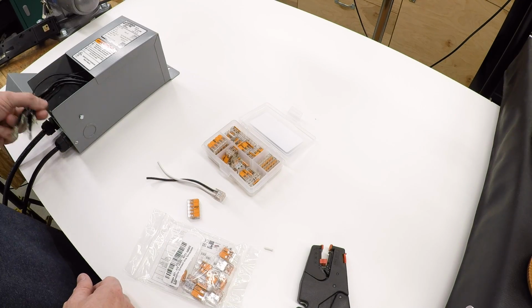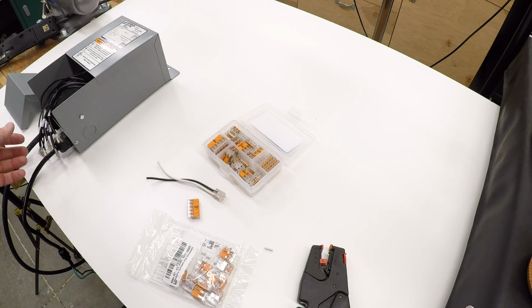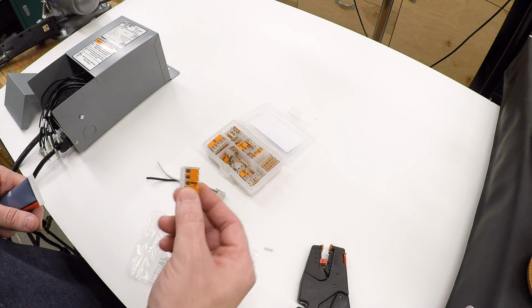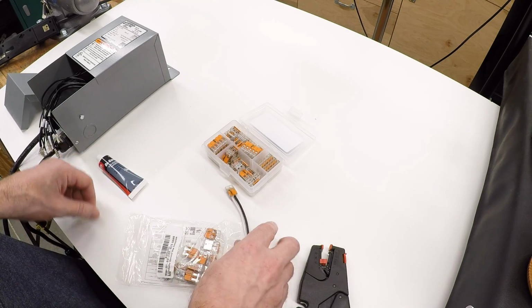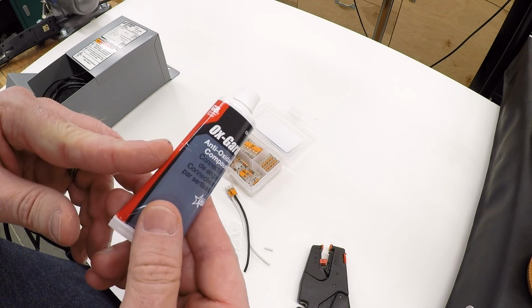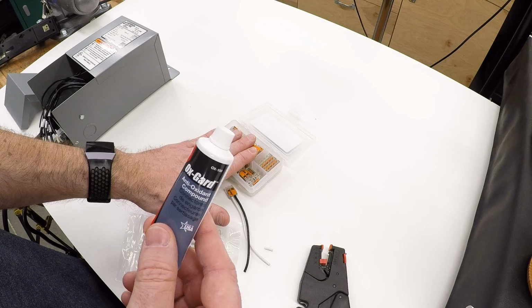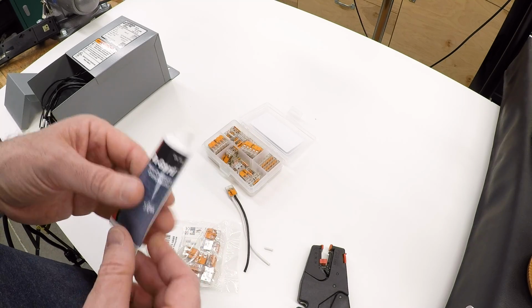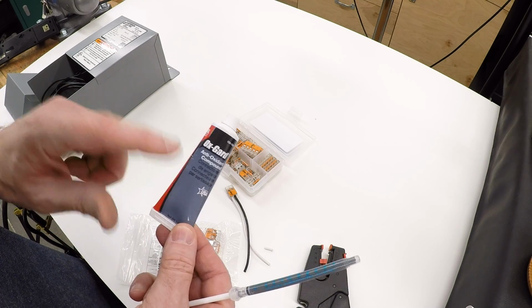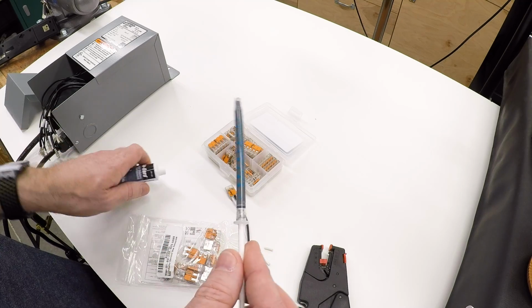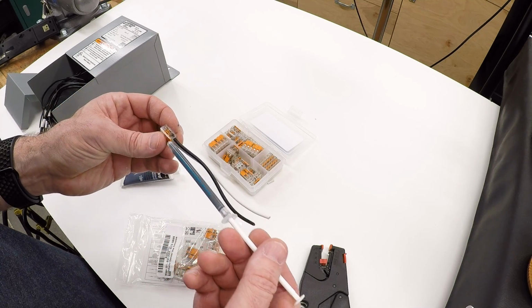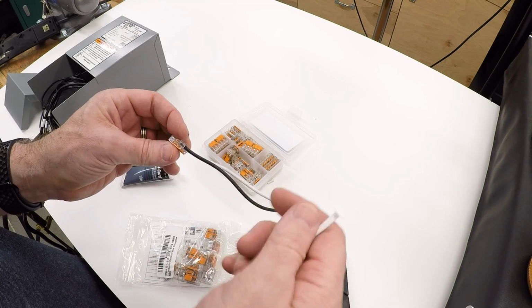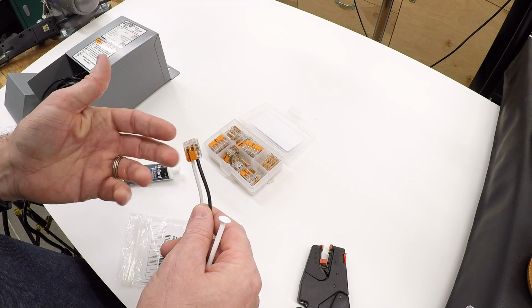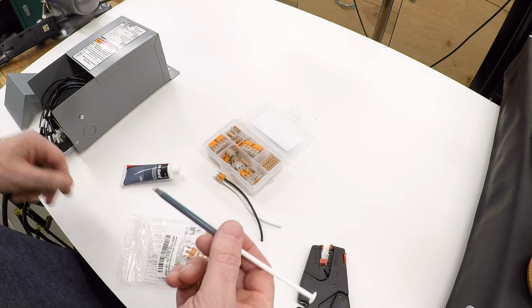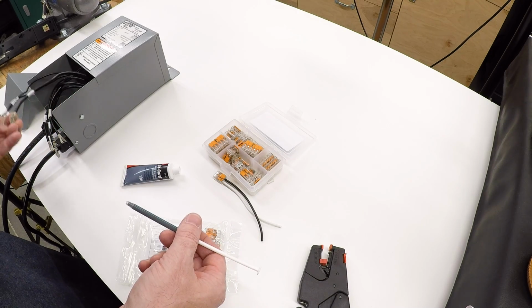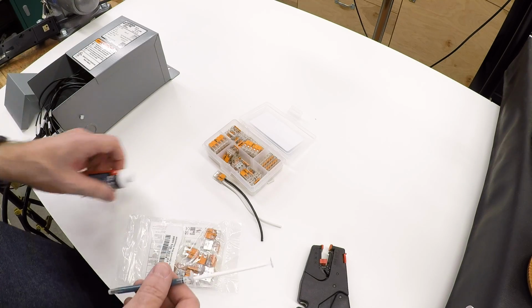One thing about this is that this transformer has aluminum wire. To make aluminum wire connections to nuts like these that have copper, you have to use some kind of corrosion-inhibiting paste. This one is called Oxguard. Wago actually makes their own that comes in a syringe, but I didn't have any available locally and would have had to mail order it. So I picked up this Oxguard and put some in a syringe. I'll squirt a little down into the wire nut, as called for by the instructions, before inserting the wire, at least for the aluminum connections, to make sure they're fully protected from oxidation. Otherwise, the aluminum against the copper will oxidize over time, build up, and start to overheat and melt things, and that's bad.